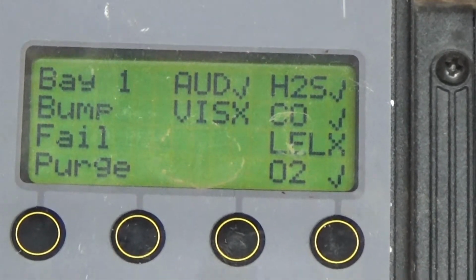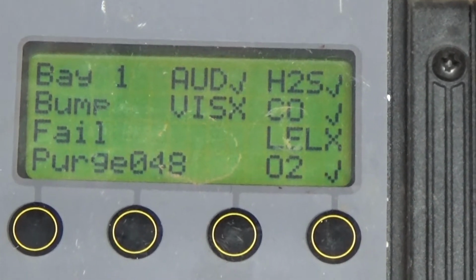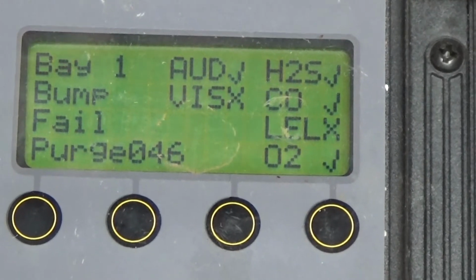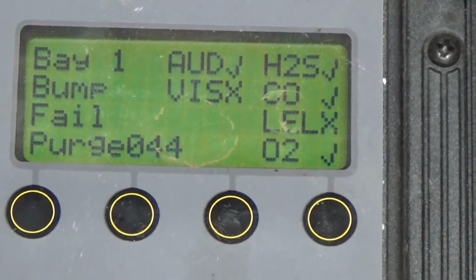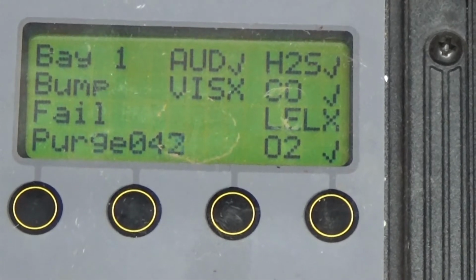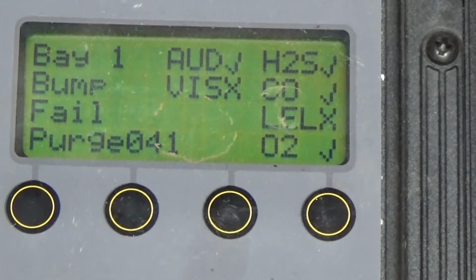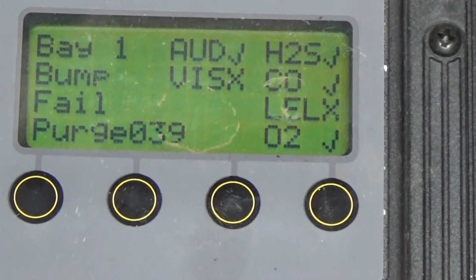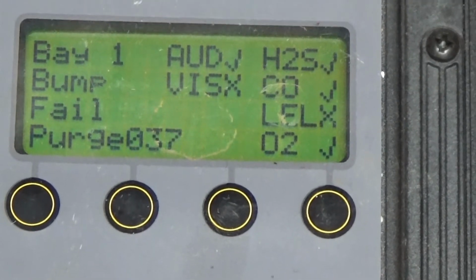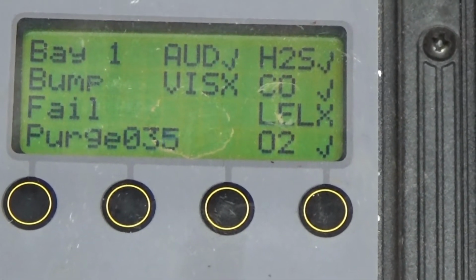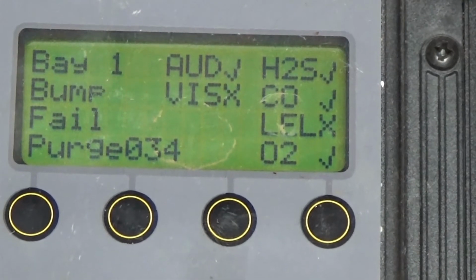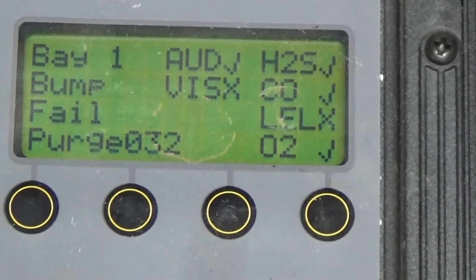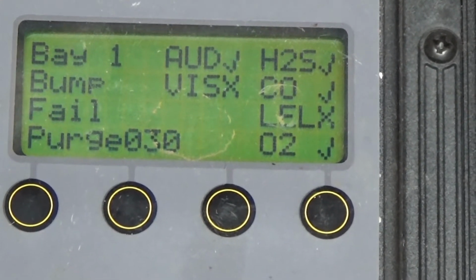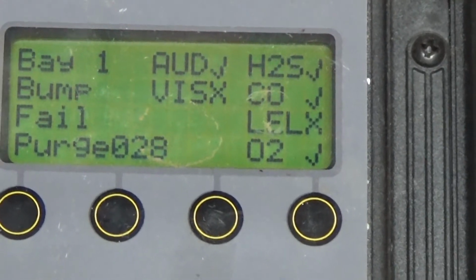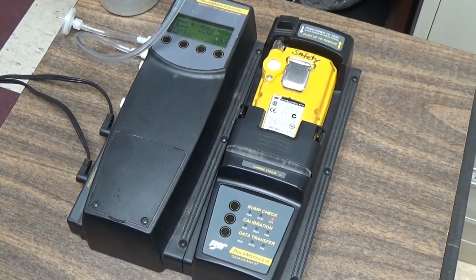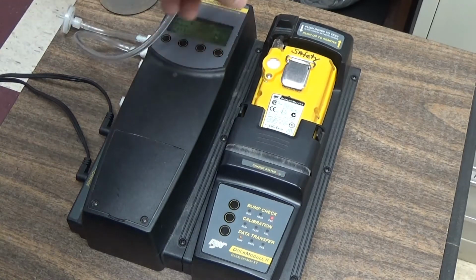As you can see, this meter has failed in a couple areas. It's failed on the visual and it's failed on the LEL sensor. After it applies the gas to the meter, it'll go through a 45-second purge period to push all the gases out of the meter to where it just has fresh air. Let it purge all the way through before you take the meter out of the bump station. After the countdown is complete, remove the meter from the bump station.